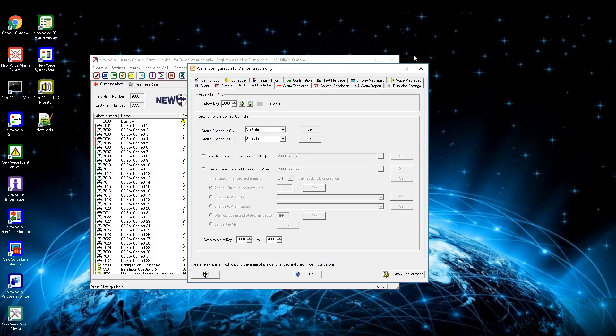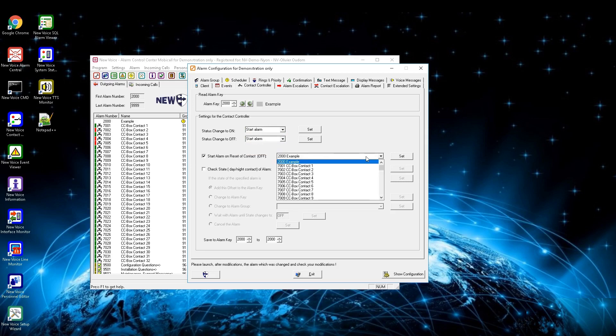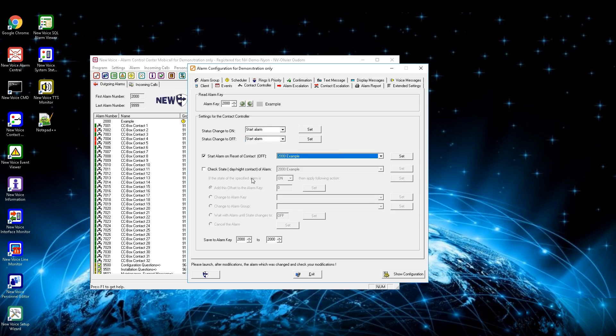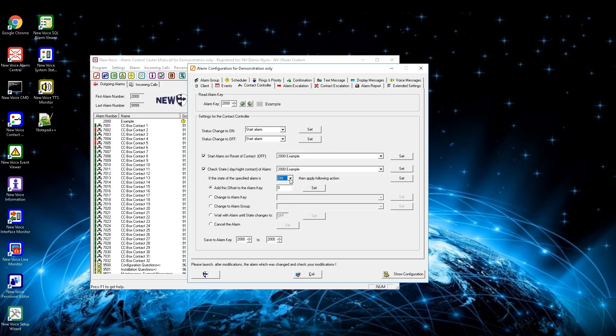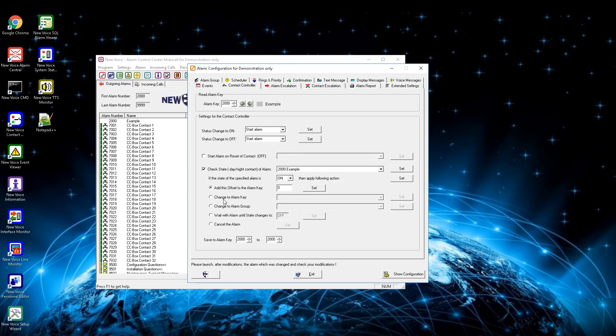Within the contact controller settings window you can define what should happen on a change of the contact status. The contact must be assigned to the alarm you are defining. By default, when the status changes to on the alarm is started, and the same applies to a status change to off. You can choose between nothing, start alarm, and reset alarm. By activating the box below you can define an alarm to be launched if the contact status gets reset to off. By activating the next checkbox you can check the status of a day and night contact — once active you can define the alarm status as on or off, continue with an offset, change to another alarm key or group, wait until the state changes, or cancel the alarm.